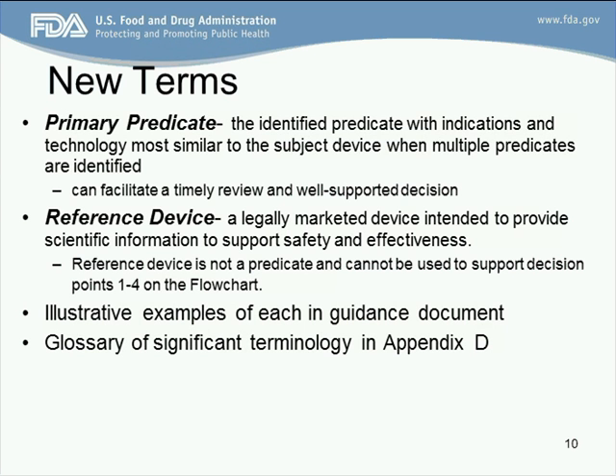Other terms that may not sound familiar are, 1, multiple predicates, which is where 2 or more predicate devices have been provided to support an SE decision. If using multiple predicate devices to demonstrate substantial equivalence, each predicate device must have the same intended use as the new device, and any different technological characteristics between the new device and the predicate must not raise different questions of safety and effectiveness. Multiple predicates can also include devices such as a multi-parameter monitor and a device construct. Examples are available in the guidance document.